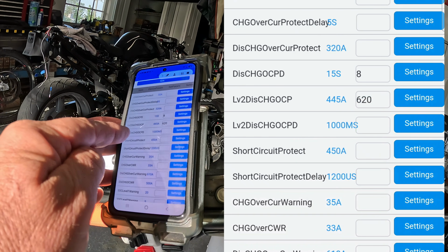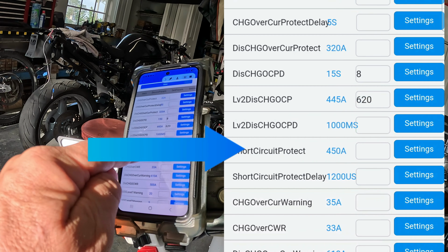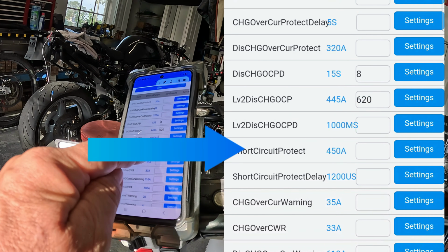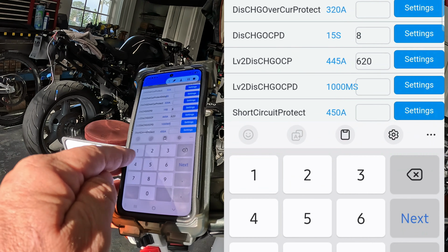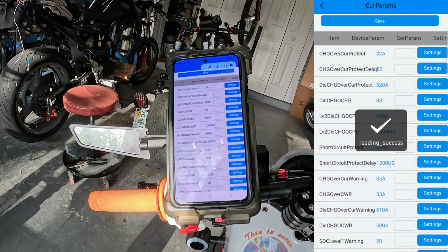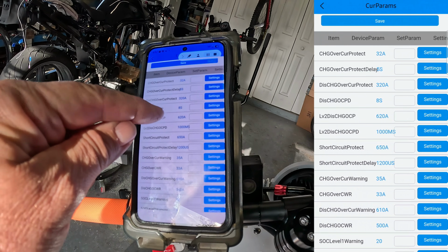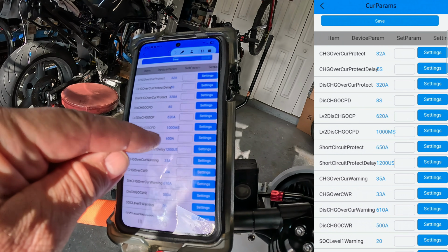Now the problem is I've got the short circuit protection set at 450 amps. I need that a lot higher, so I'm going to run that to about 650. There we are. I can go to 620 for 8 seconds, and I can hit 650 as a spike for a millisecond.